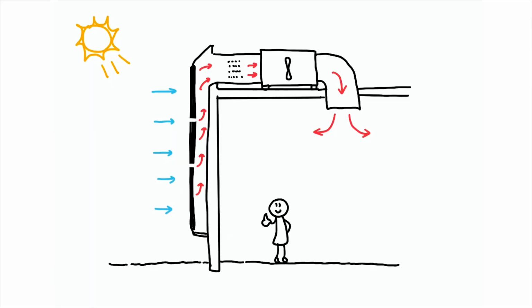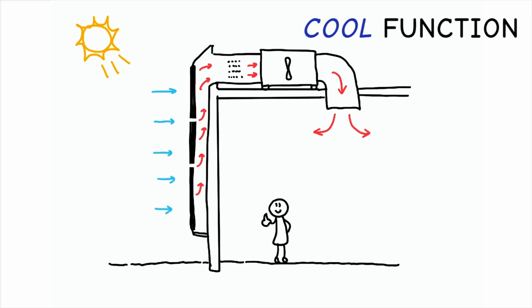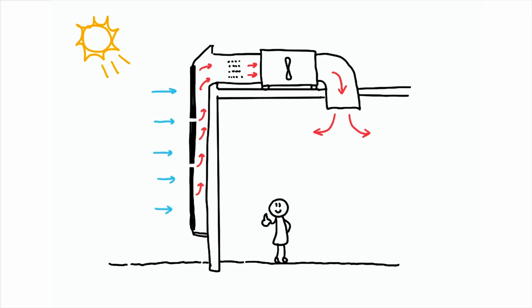Solar walls not only save energy by reducing heating costs, but they also surprisingly provide a cooling function for the building in the summer. During summer months, when no additional heating is needed, solar walls act as a shield by absorbing solar energy that would otherwise heat up the building facade, and allow heated air in the cavity to be vented off. This is beneficial for thinner walls that are in direct contact with both the interior and exterior, such as some industrial buildings.